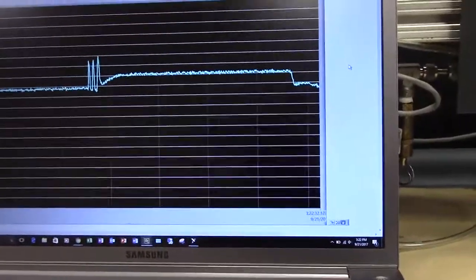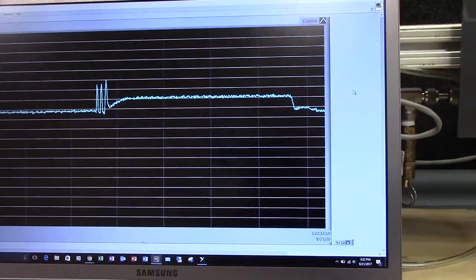Now we've just seen that the liquid is flushed back through and we have our pressure gain drop down actually slightly below set point again which shows that now the mixed phase portion of this is done. What this highlights is that this regulator was not able to handle the mixed phase fluid while keeping inlet pressure steady and shows that you have irreversible pressure gain and loss when you have this changing density moving through the regulator.